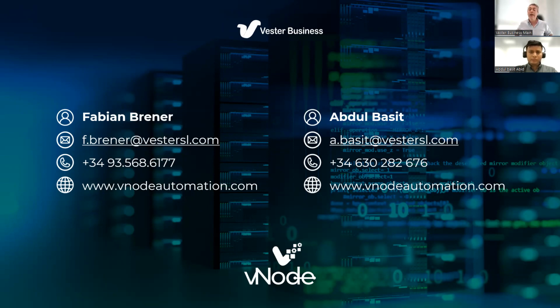It takes some experience, and our experience says that you can move data from one side to another, 1 second is secure, yes. Less than that will depend on many components. Probably you can try 100, 150 milliseconds. It is something you need to experiment with on your own network and your own devices, all right?